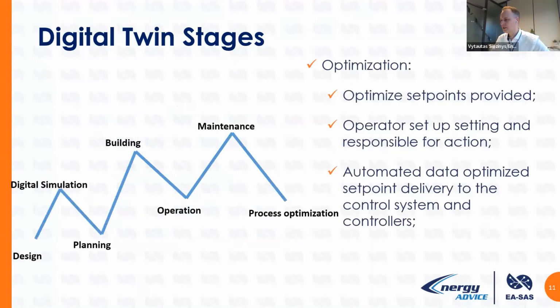Coming back to optimization, in fact, optimization means that we need to optimize set points, as a very easy example about the temperature, the question is 60 degrees or 59 degrees. It's what temperature we need, in fact, as a set point, or pressure. Is it 1.5 megapascal or 1.4 megapascal as the set point? It would affect the system behavior, and the yield and efficiency, etc. So finally, all these set points in the SCADA system, in the control system, would be somehow changed by operators.